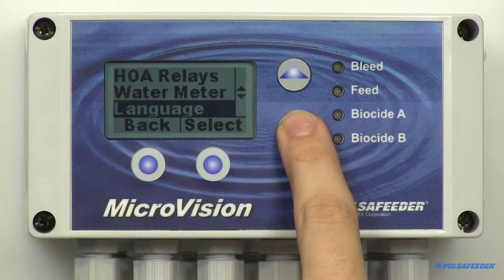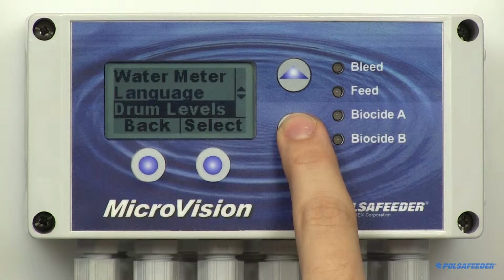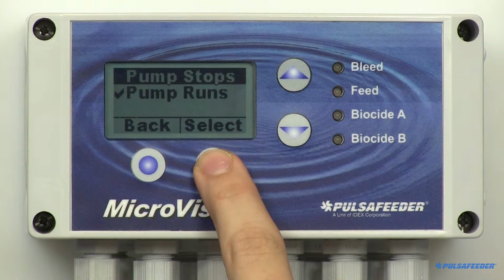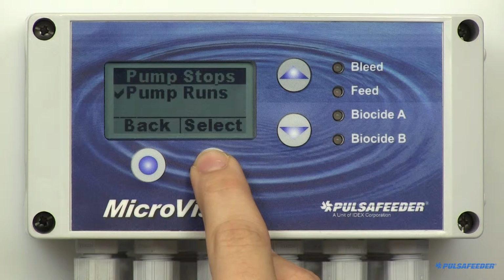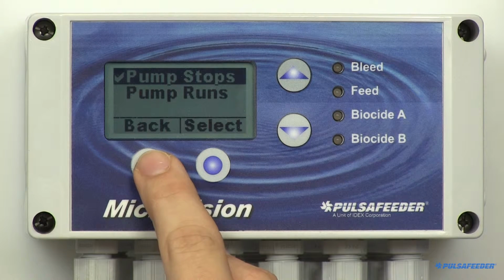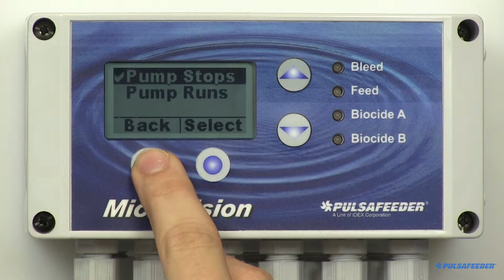Arrow down and select drum levels. The MicroVision has four drum level inputs, one for each pump. To make your selection, highlight it and press Enter, and the screen will display a check mark. Note that refilling the drum may cause the pump's relay to energize without warning.